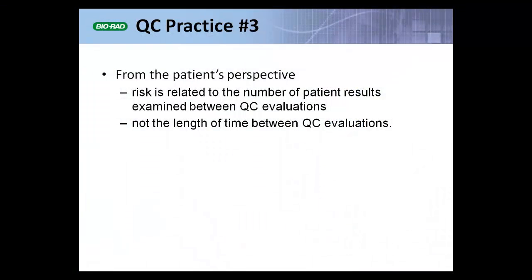It's a natural way for us to think about it and fits naturally into laboratory workflow. But from the patient's perspective, risk is related to the number of patient results examined between QC evaluations, not the length of time between QC evaluations.